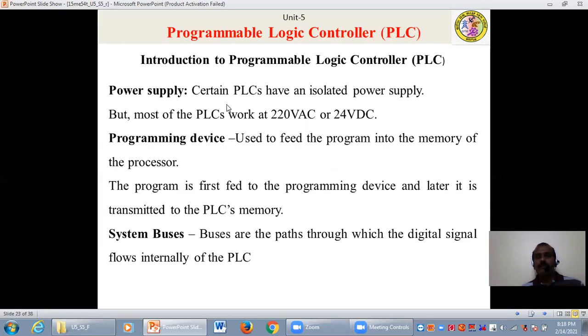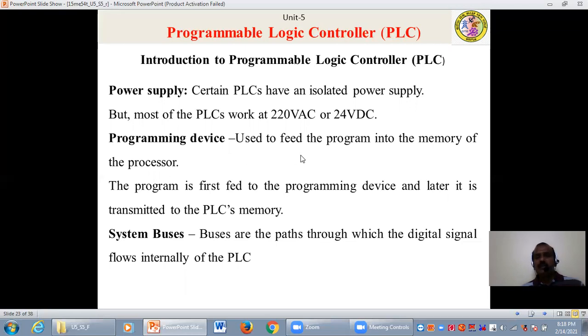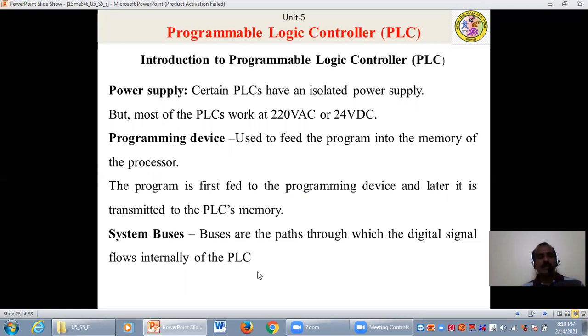Power supply: certain PLCs have an isolated power supply, but most PLCs work at 220 volt AC or 24 volt DC. Programming device: it is mainly used to feed the program into the memory of the processor. The program is first fed into the programming device and later transferred to the PLC's memory. System buses: buses are the paths through which digital signals flow internally in a PLC.